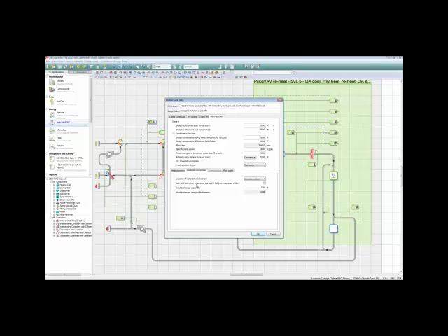It'll end up constraining the chiller or something, or just not be returning significantly colder water, at which point it'll automatically shut down, and now the chiller is operating normally with that same cooling tower not connected in water side economizer mode, connected only as heat rejection for the condenser loop. If I tick this box, there will not be integrated operation.